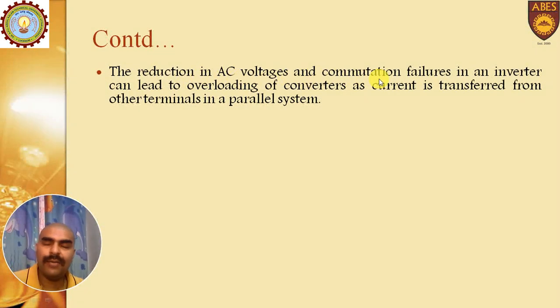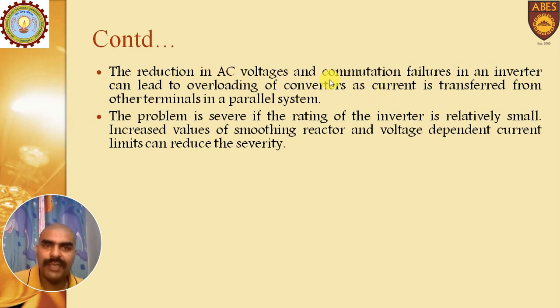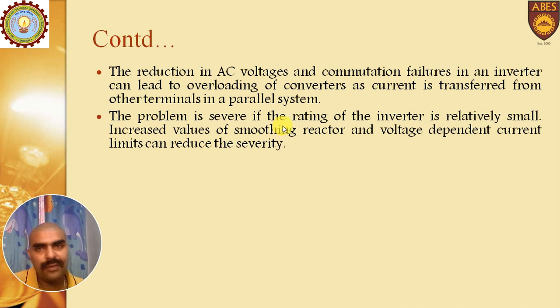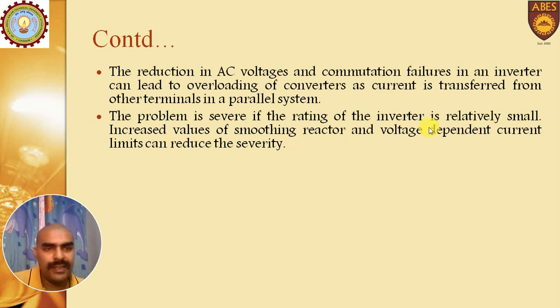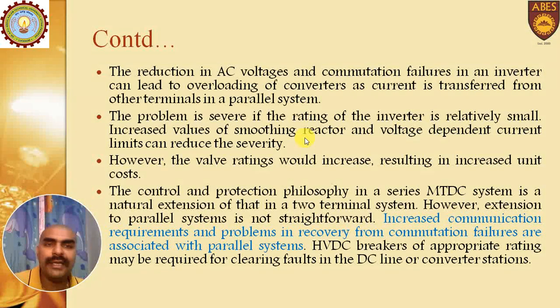The reduction in AC voltage and commutation failure in an inverter can lead to overloading of a converter, as current is transferred from other terminals in a parallel system. If there is any commutation failure, this may lead to overloading of the converter. This problem will be more severe if the inverter rating is small. Increased value of smoothing reactor and voltage dependent current limits can reduce the severity, but they will increase the extra cost of a parallel MTDC system.